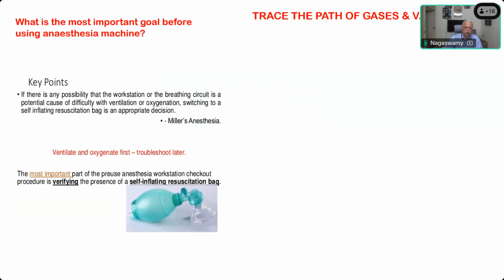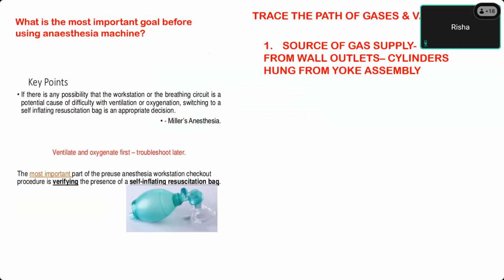Now, can you trace the path of the gases, oxygen and other anesthetic agents, from the point of delivery to the machine to the patient? Starting from high pressure systems, sir, from the machines, from the cylinder, yoke assembly, pin index, yoke assembly, and crossing the pressure regulator. So the first point is the source of gas supply. Identify whether it is from the wall outlet or from the cylinder attached to the yoke assembly. This is the first thing we trace.